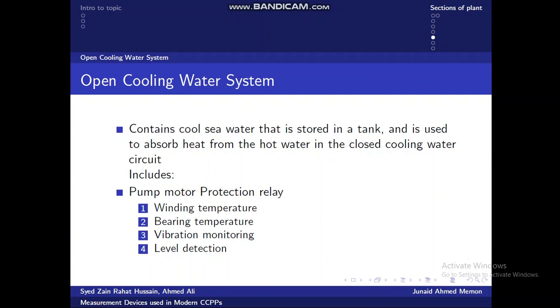Next, we have the open cooling water system, which contains cooled seawater that is stored in a tank and is used to absorb heat from the hot water in the closed cooling water circuit. So the closed cooling water circuit is what is in contact with the different devices and the different equipment. So that closed cooling water absorbs the heat from it, not in direct contact, but the pipes are close to the equipment. And then that closed cooling water comes to the open cooling water circuit where it absorbs the heat from the water, and then it is deposited out into the sea.